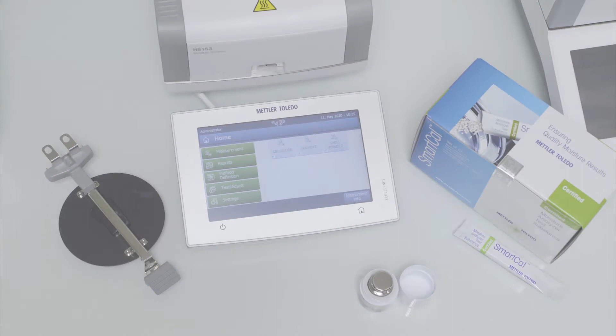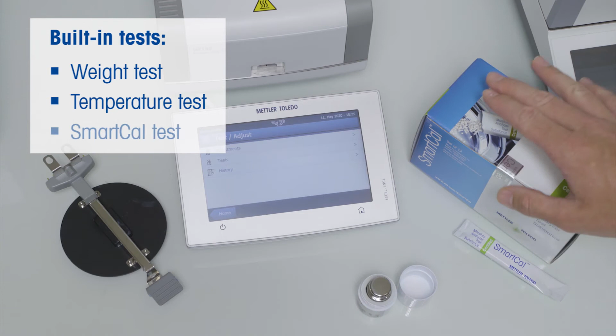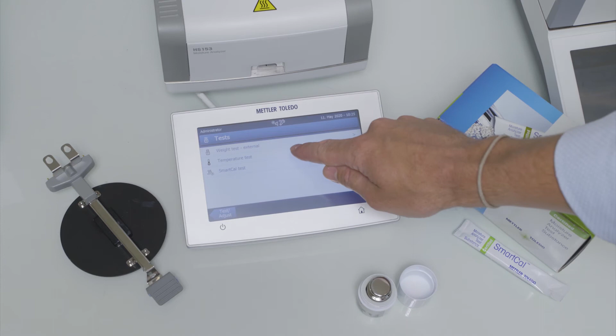A moisture analyzer can be tested in 3 ways, and each test is relevant. Test of balance, heating unit, and overall instrument test. For every performance test, there is a specific equipment available, and depending on the moisture analyzer type, the procedure is automated, simpler, faster, and documented.